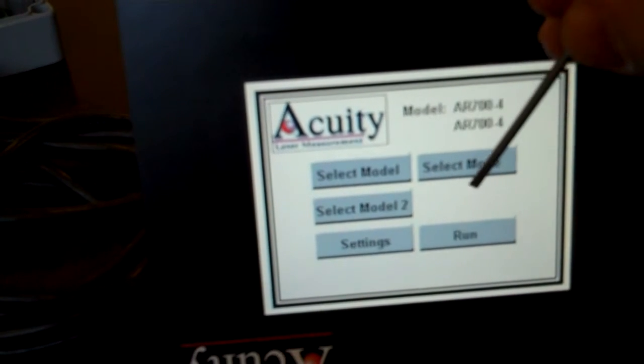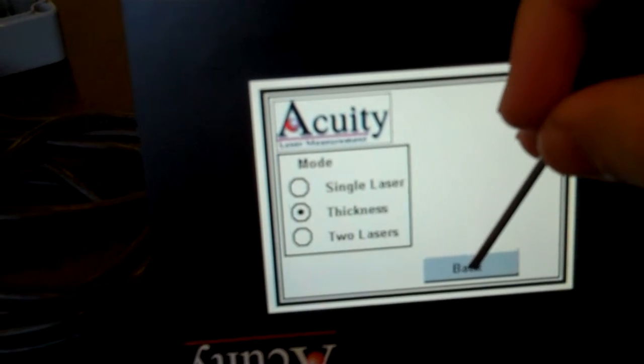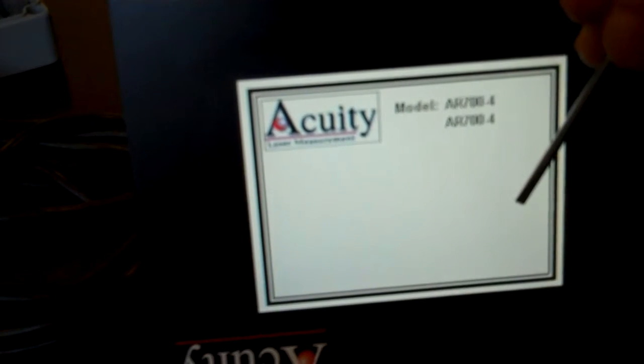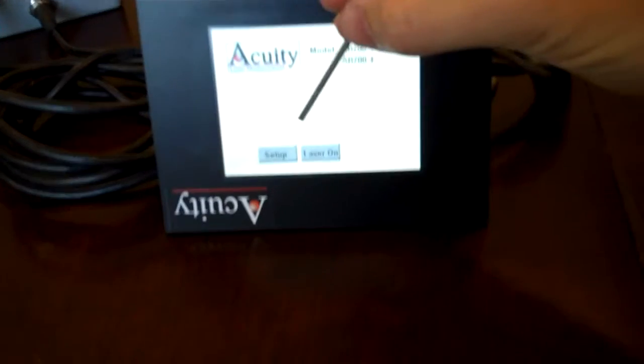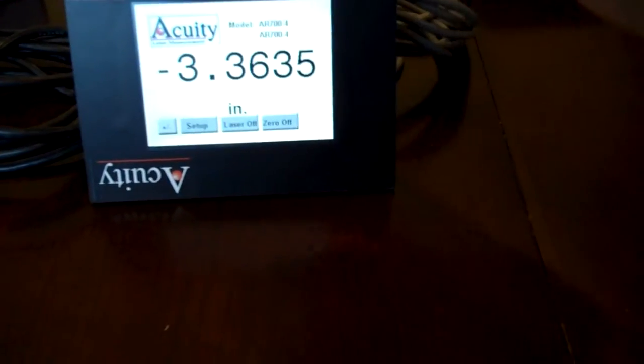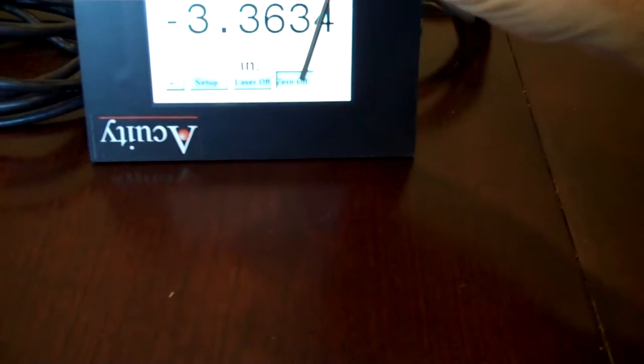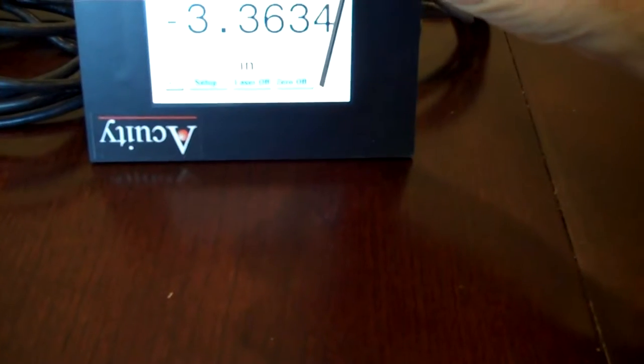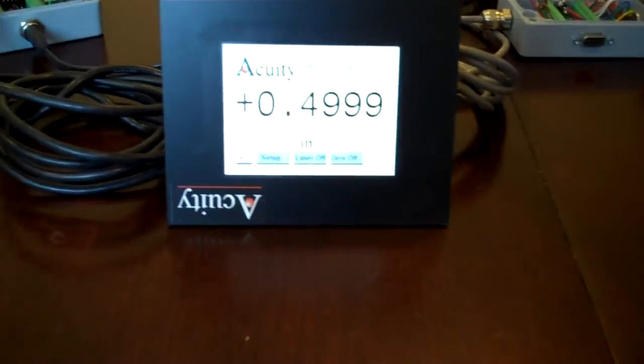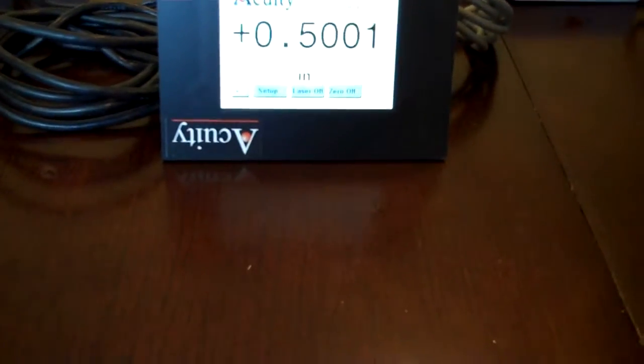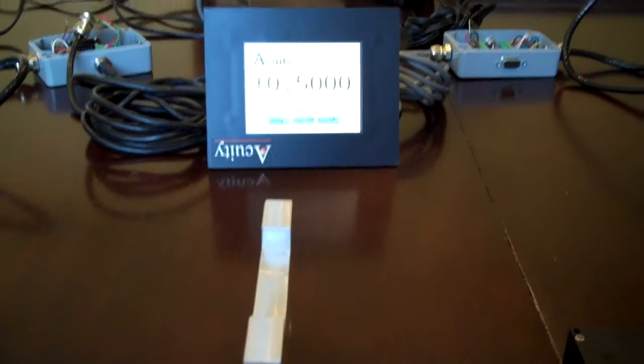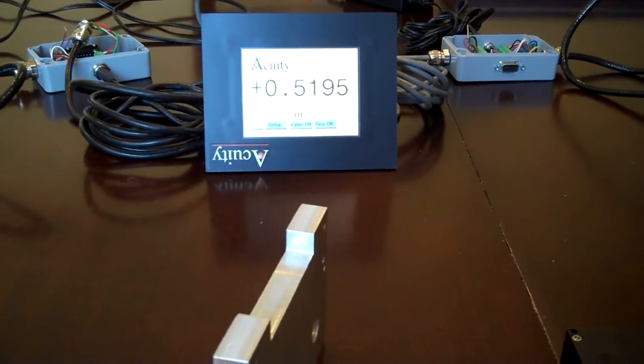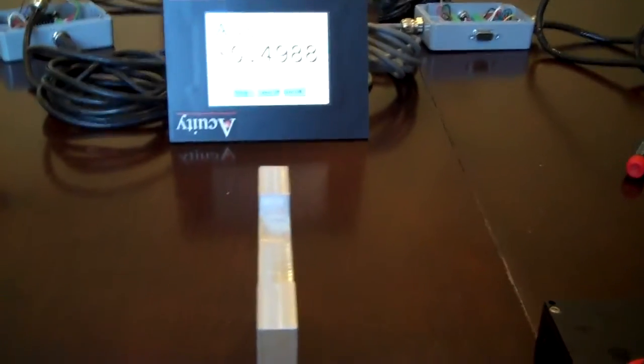Go to select mode. Thickness mode. Run. Laser on. And you'll see a number which doesn't make sense but once you hit zero, you might have to hit it twice. Auto zero. The number should read the thickness of the offset that you placed in there. And you can see that the number will change as you move the block.